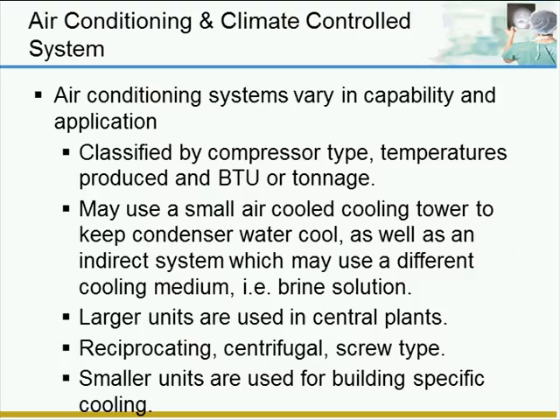Typical AC systems are classified by the type of compressor that operates them. You'll have the temperatures that they produce and the tonnage, the BTUs that they put out. AC systems will utilize small cooling towers or condensers. They might also have indirect systems, which will feed brine solution or another medium into a cold storage or different location, depending on what it's being used for. The larger units are in central heating and cooling plants, while smaller units are typically package units, which will be on the roof. These are common for IT rooms, emergency rooms, and kitchens, where you need a dedicated cold storage unit. Common compressor types are reciprocating, centrifugal, and screw type units.